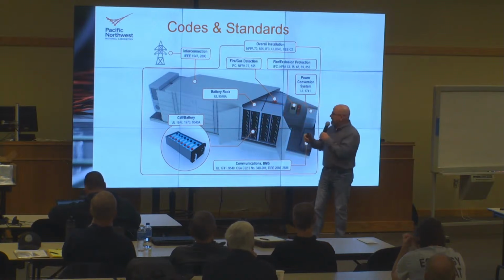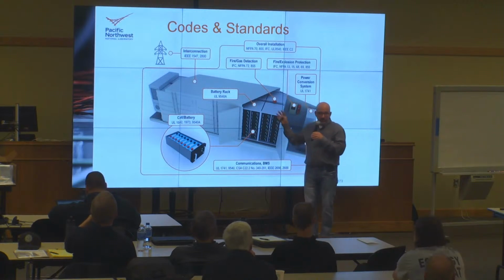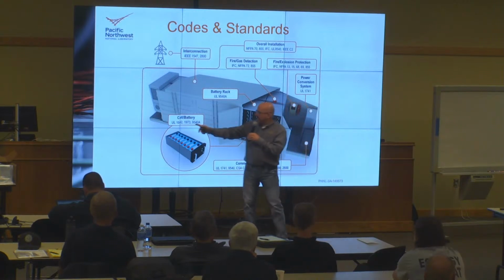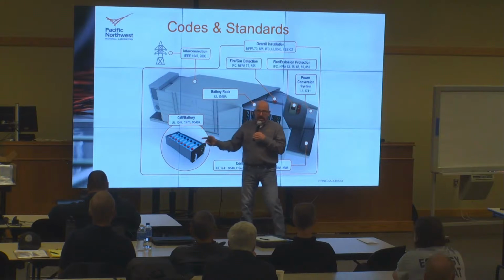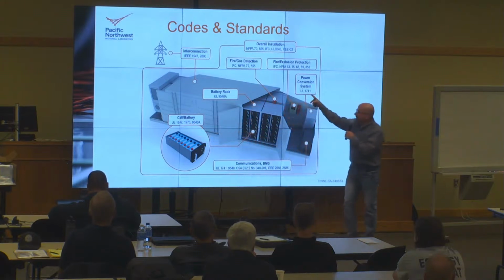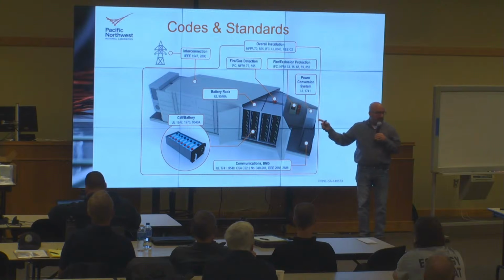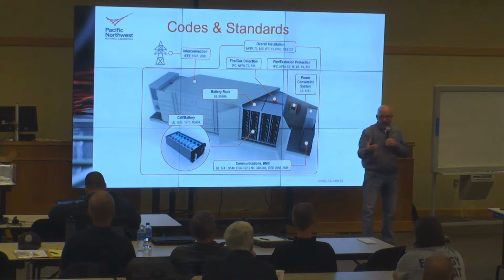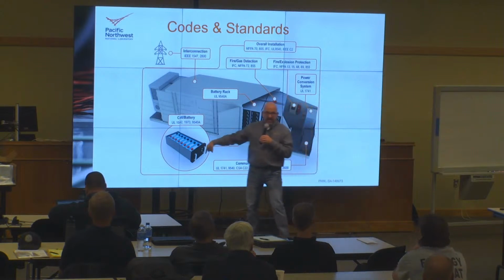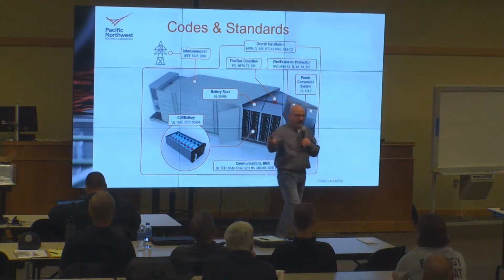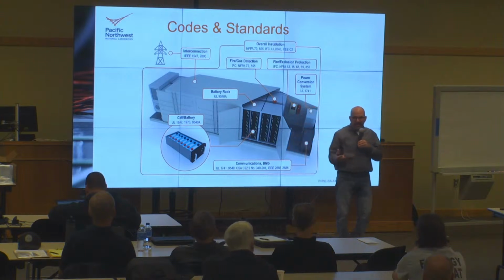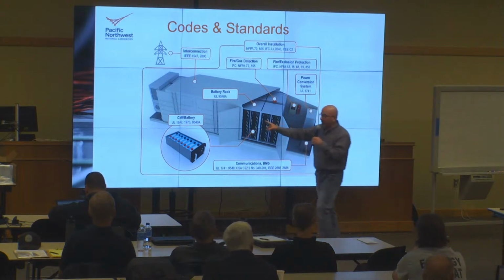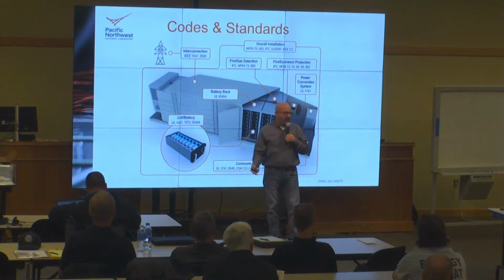Here's an important part: to be listed to 9540, you have to start with a 1973 listed battery and pair it with a 1741 listed inverter. And that right there is one of the barriers to a second life battery getting off the ground, because these are batteries coming from vehicles that are not listed to any of these. So right from the get-go, that battery doesn't have that listing to ever get it. Plus, you're never going to fire test it because it's a destructive test.